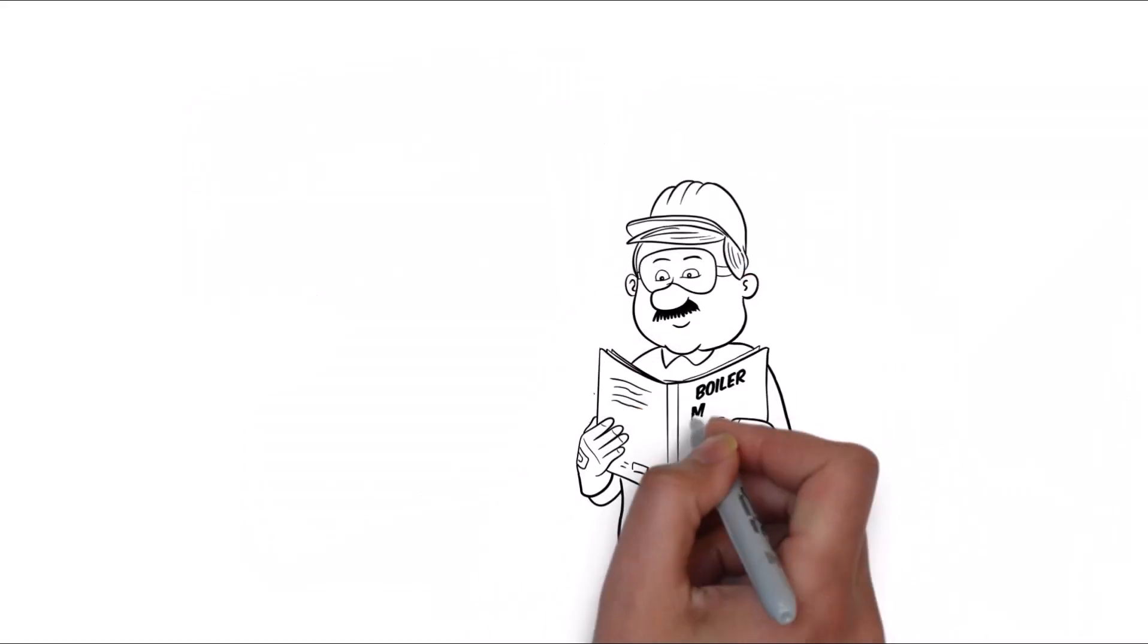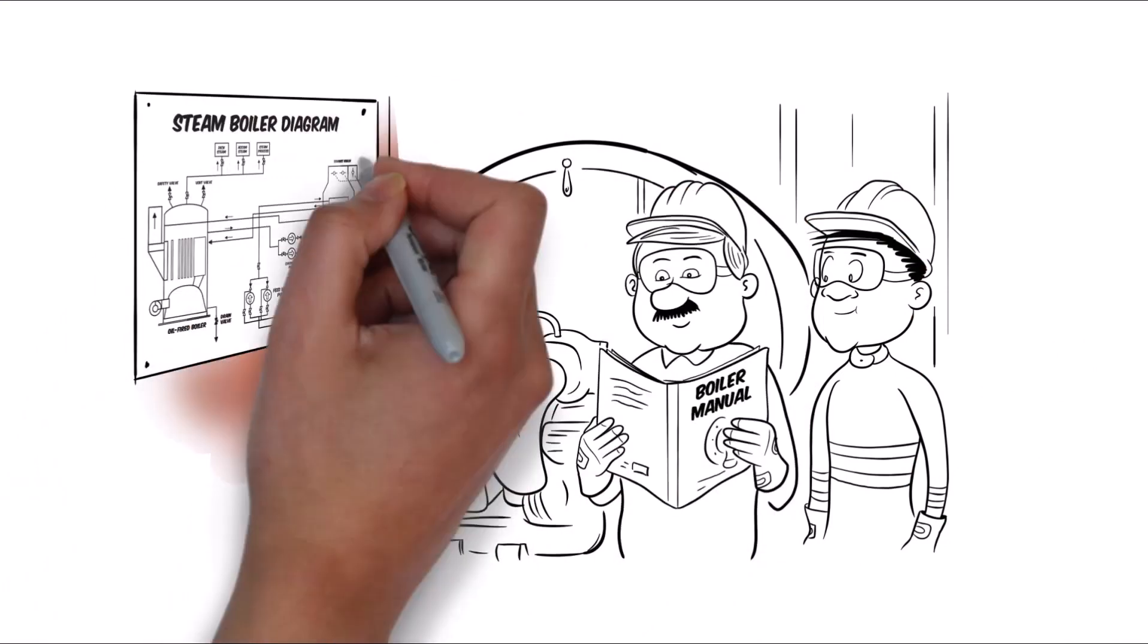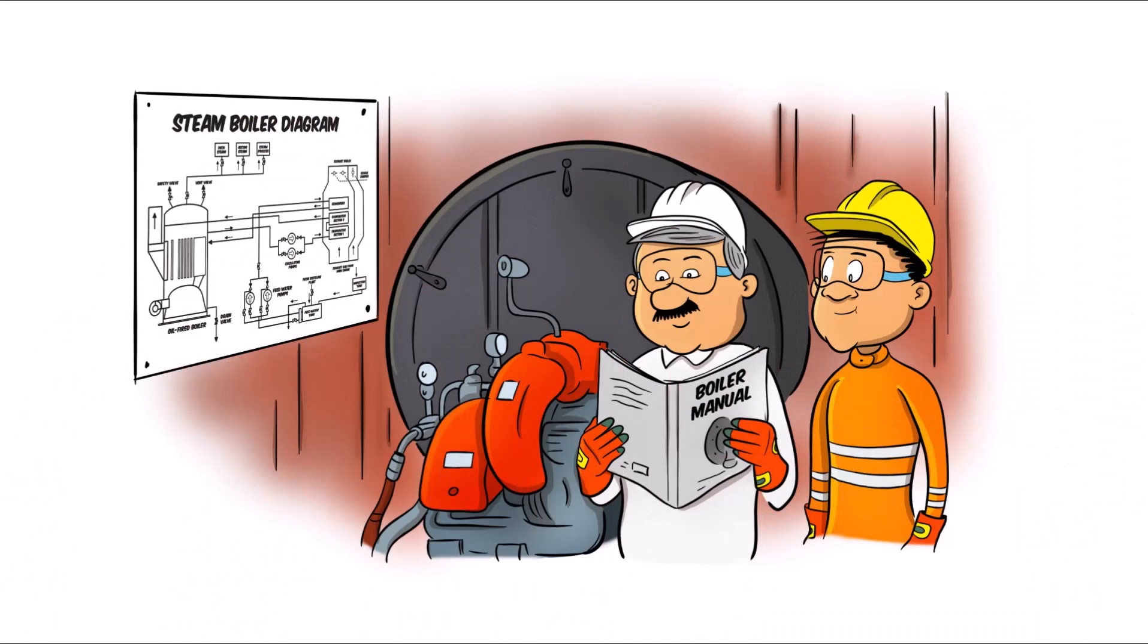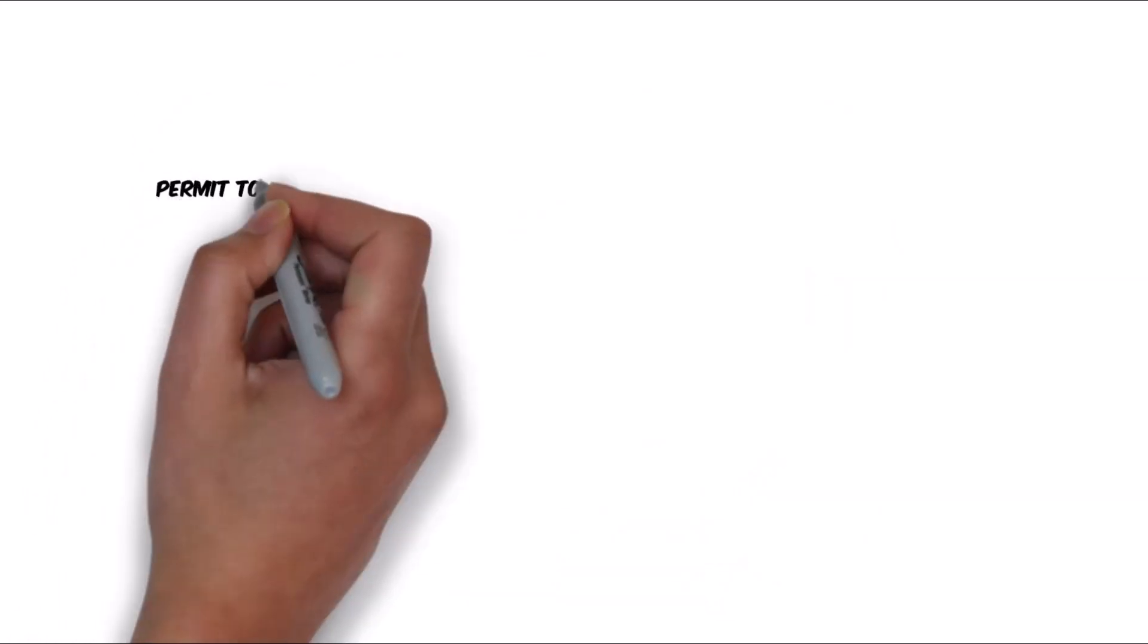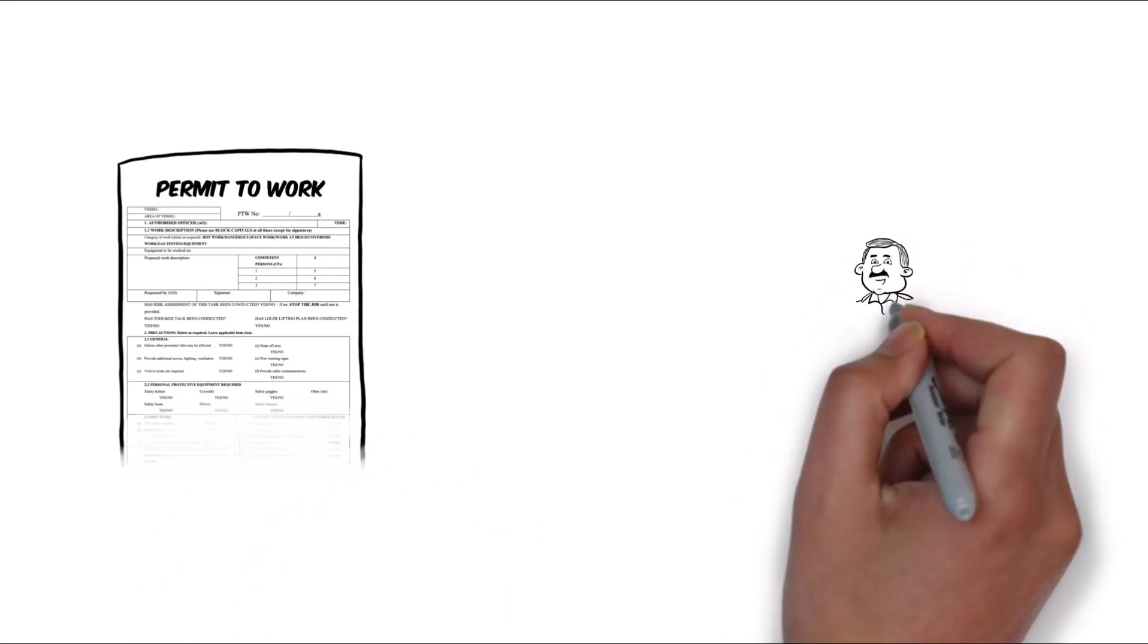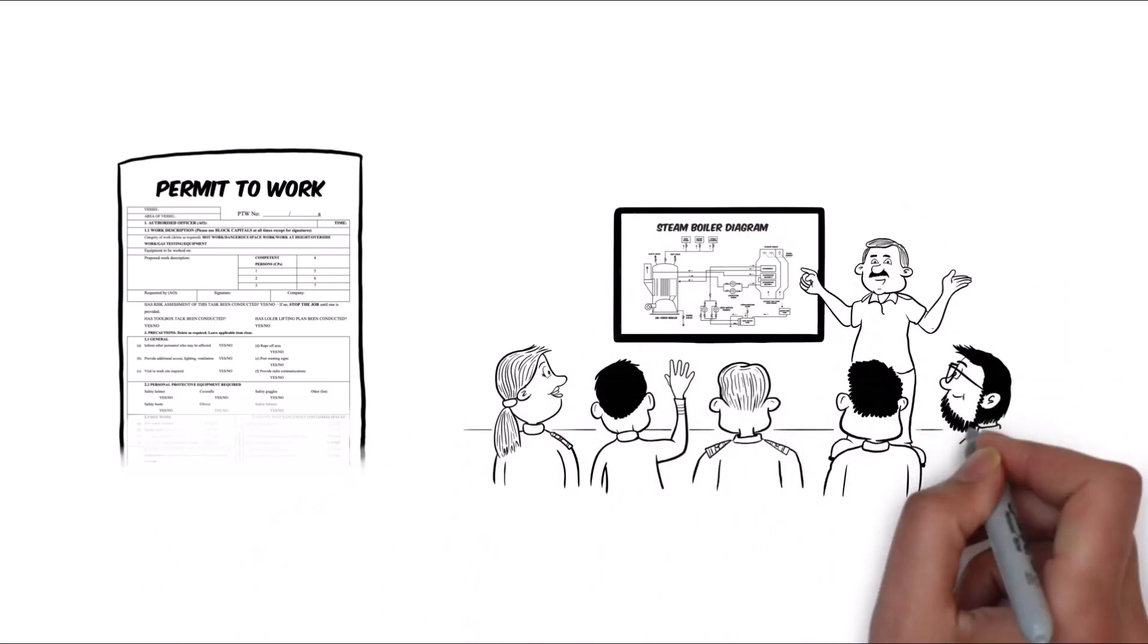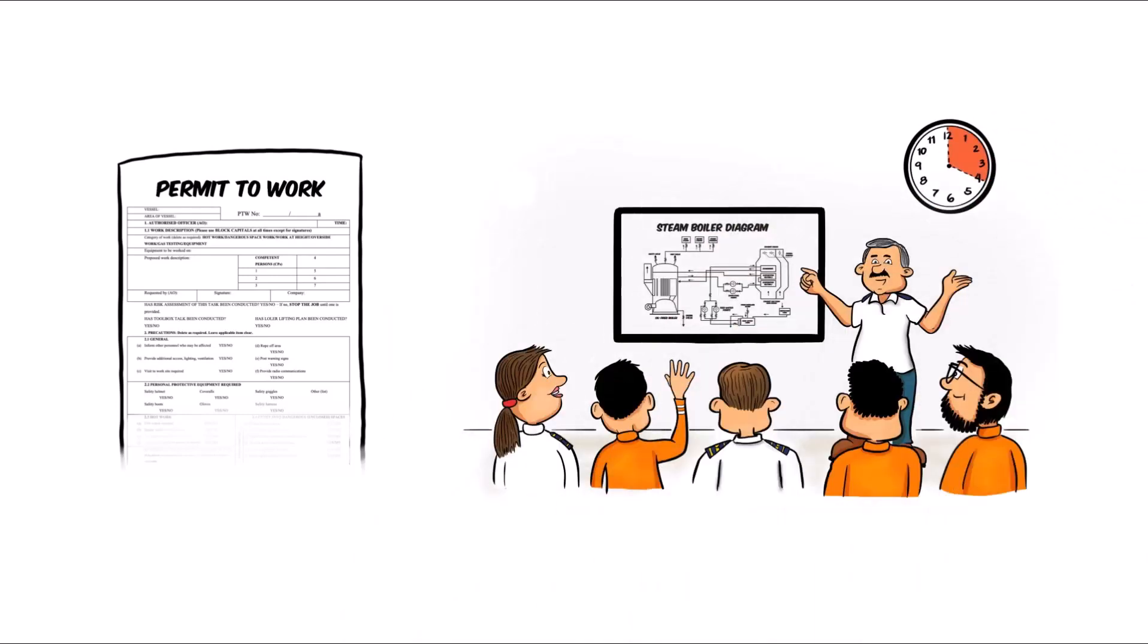Detailed planning is important when preparing for maintenance tasks. Review equipment manuals and system drawings to identify hazards. Carry out a formal risk assessment, inform the deck department where appropriate. A permit to work must be issued by a senior engineering officer. Carry out a toolbox meeting immediately prior to starting the task.